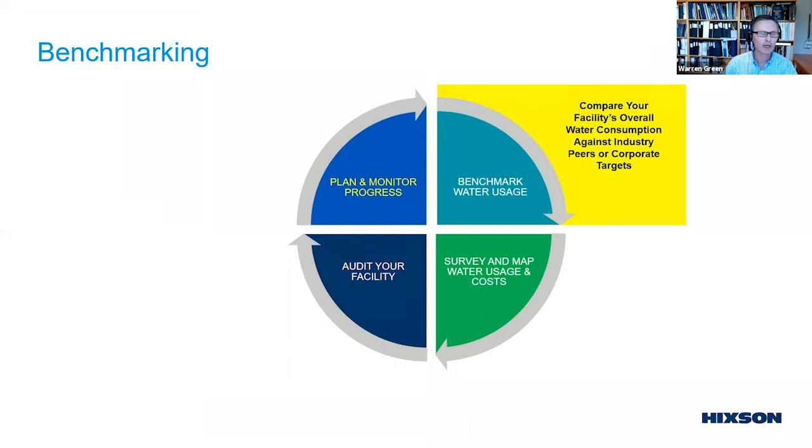The common benchmark is the Water Use Ratio, or WUR — also called the wastewater use ratio — benchmarked by Hixson and by the industry across various segments. At a high level, it is simply the total water you buy divided by the total amount of product you produce, either as a gallon-to-gallon ratio or a gallon-to-pound ratio.